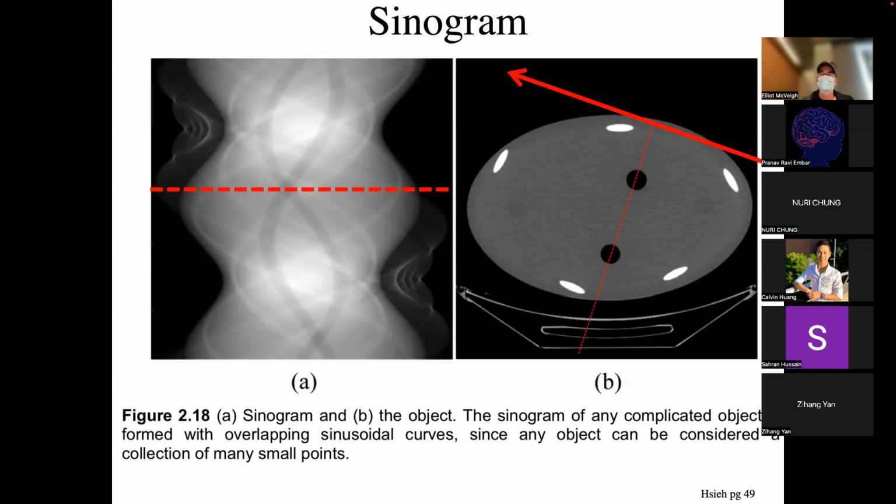other than themselves. So if this was a very high attenuator, it would basically just occlude my view of all of these at this specific angle. So you get these data dropouts at specific angles, and this will cause artifacts that are called streaks. They just cause things to splash. And we'll see some of those later.